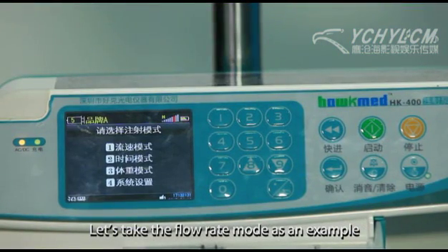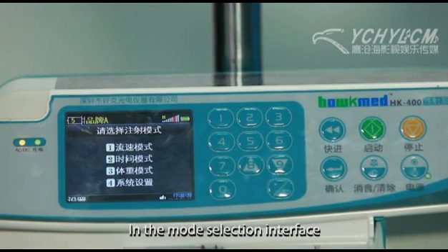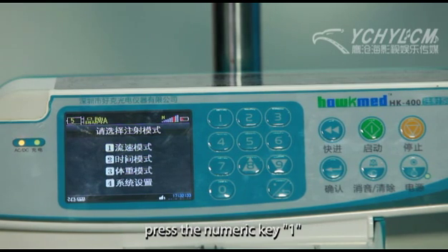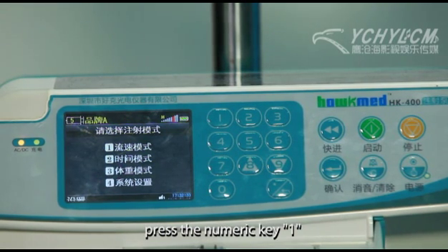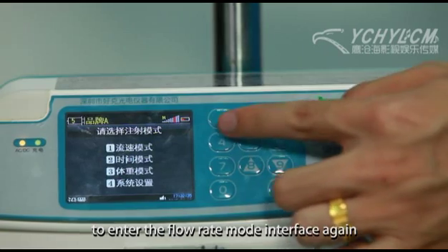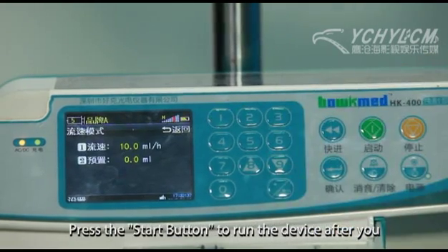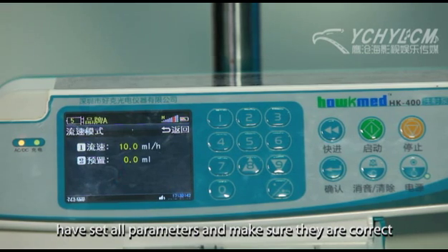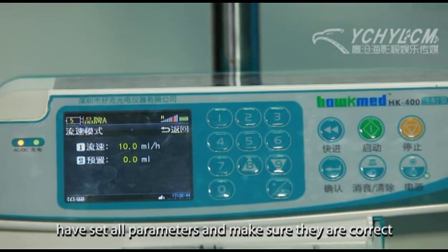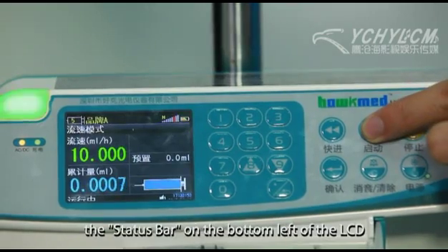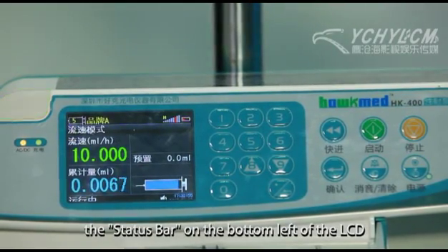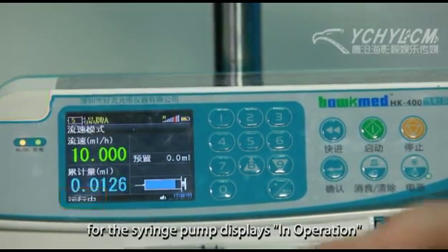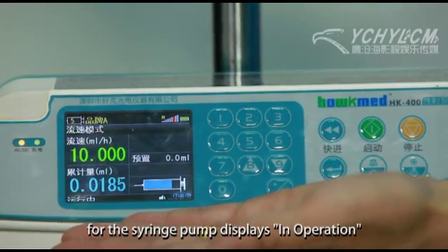Let's take the flow rate mode as an example. In the mode selection interface, press the numeric key 1 to enter the flow rate mode interface again. Press the Start button to run the device after you have set all parameters and make sure they are correct. Under the infusion state, the status bar on the bottom left of the LCD for the syringe pump displays In Operation.